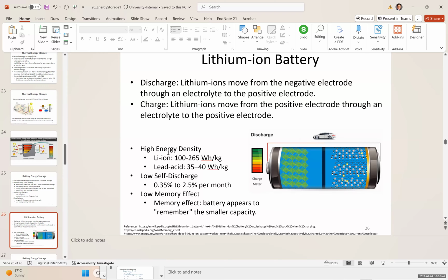We have high energy density—lithium-ion is about 100 to 265 watt-hours per kilogram, while lead acid is 35 to 40, so 5 to 6 times less. They also have low self-discharge, 0.35% to 2.5% per month—very low. You leave it for a month and it only drains 2% maximum.